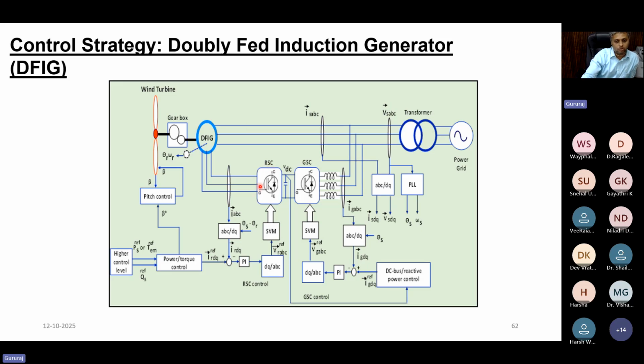But in this particular situation, for a transient duration, maybe 180 milliseconds, 200 milliseconds, or depending upon the grid codes. The German grid code suggests that for at least 150 or 180 milliseconds you need to stay connected to the grid, even in the case of zero voltage ride-through, a dead short circuit. So that imposes a severe implication, a kind of damage, on the machine side and on the converter side. Rotor speed increases because there is no way to pump out the power. There is huge accumulation, and a huge speed is seen on the rotor side.